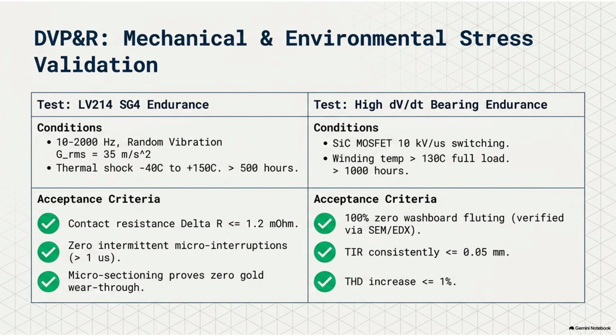The sources detail the lightning test, officially called high DVDT endurance testing. Remember the high-frequency switching stress from the inverter, the 10 kilovolts per microsecond that caused the spark? Right. They take a fully assembled motor and hook it up to a specialized, oversized testing inverter specifically designed to aggressively and relentlessly blast the motor with that exact 10 kV per microsecond electrical stress. They intentionally feed it the lightning.